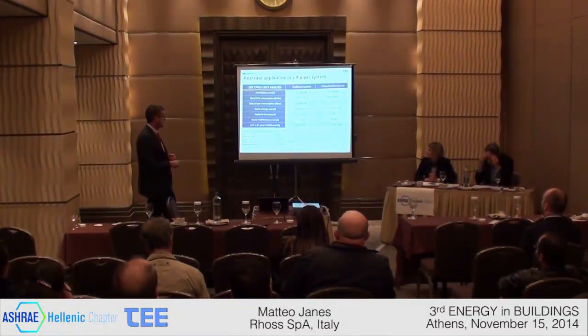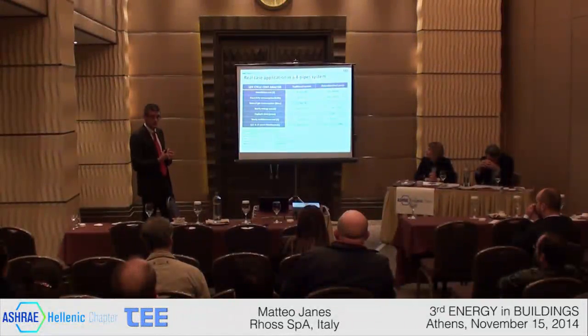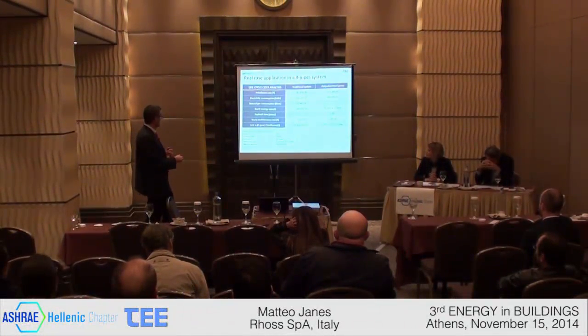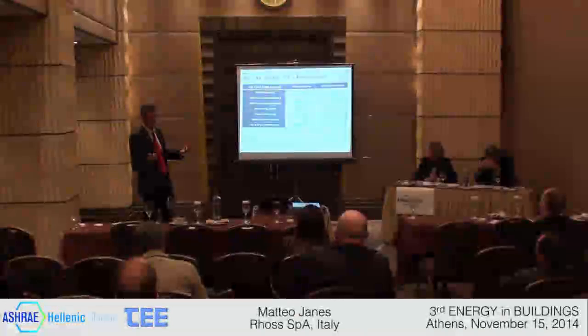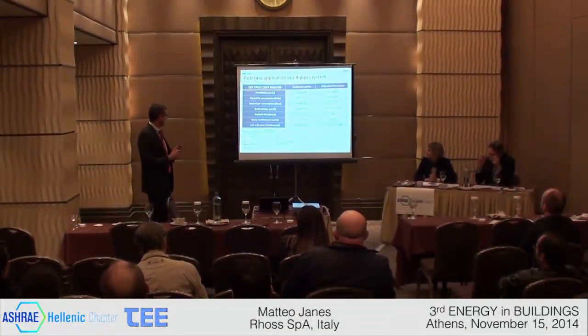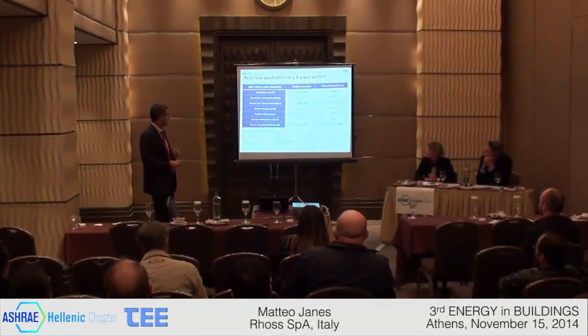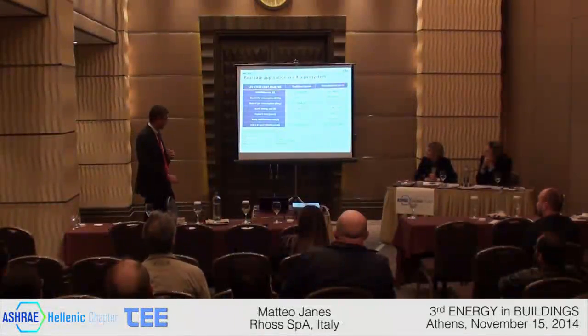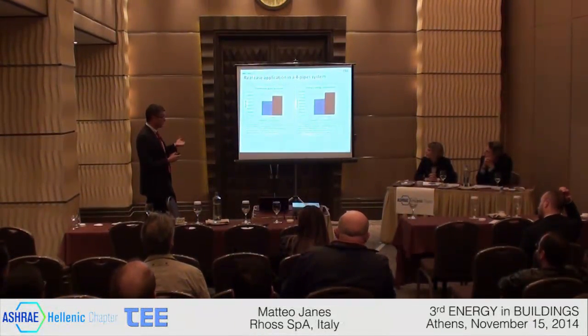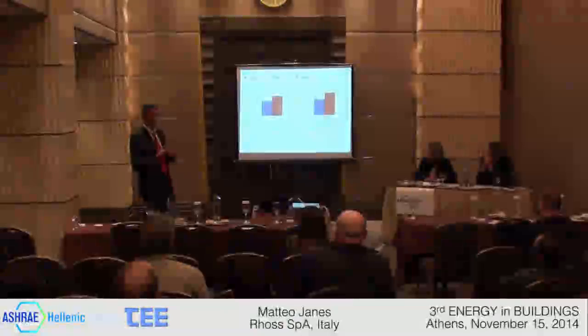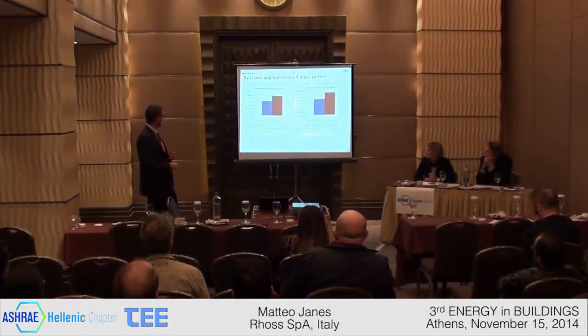Maintenance is also easier because in the polyvalent heat pump case we need to maintain just one unit, just the polyvalent heat pump. In this case we have the chiller and the boiler, 2 units. And also a life cycle cost in a 15 year time frame shows a saving of about 22%. It's not only a matter of electricity bill, it's also a matter of reduction of greenhouse gas emissions and reduction of primary energy consumption.